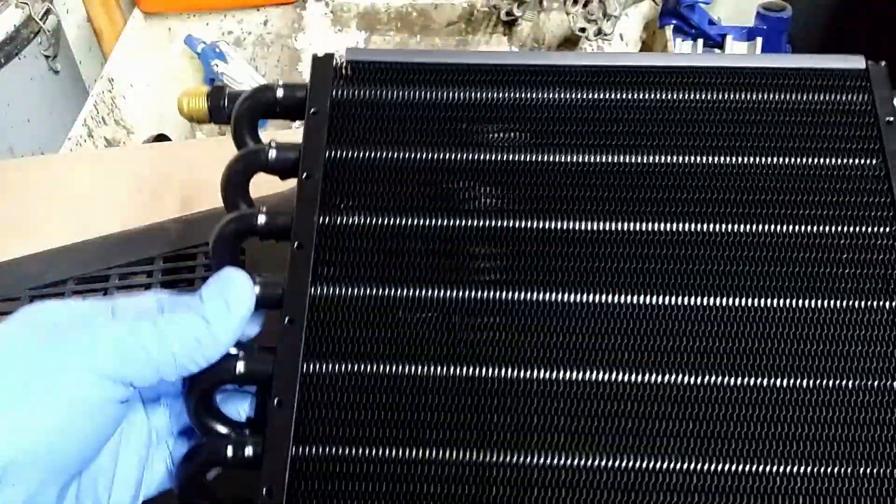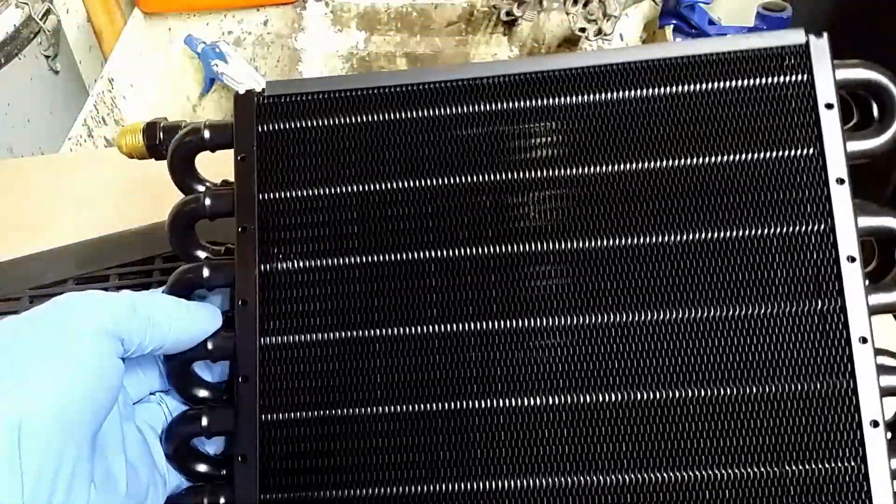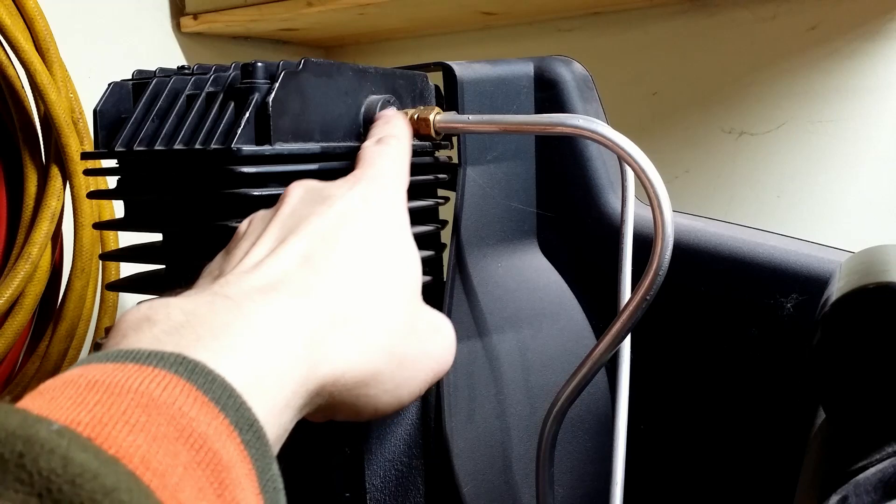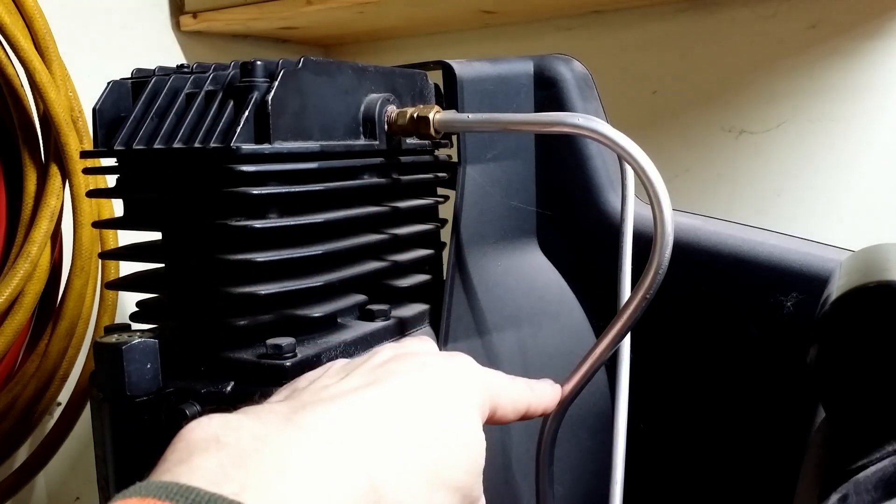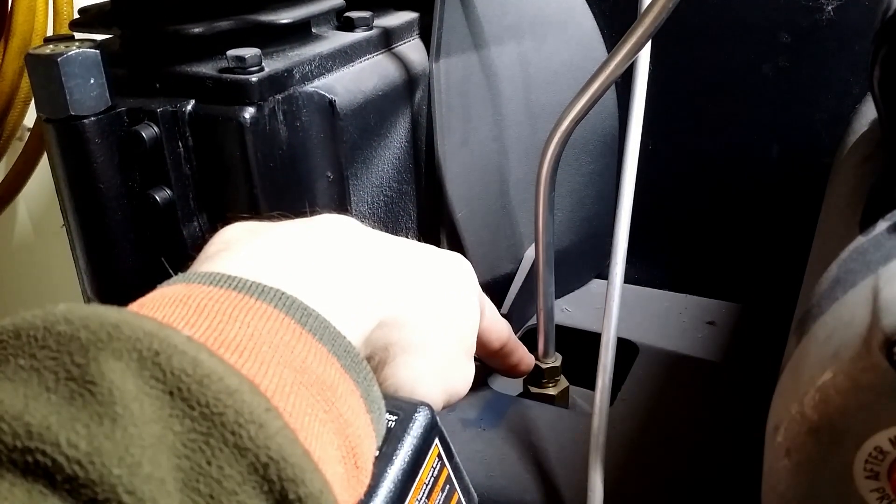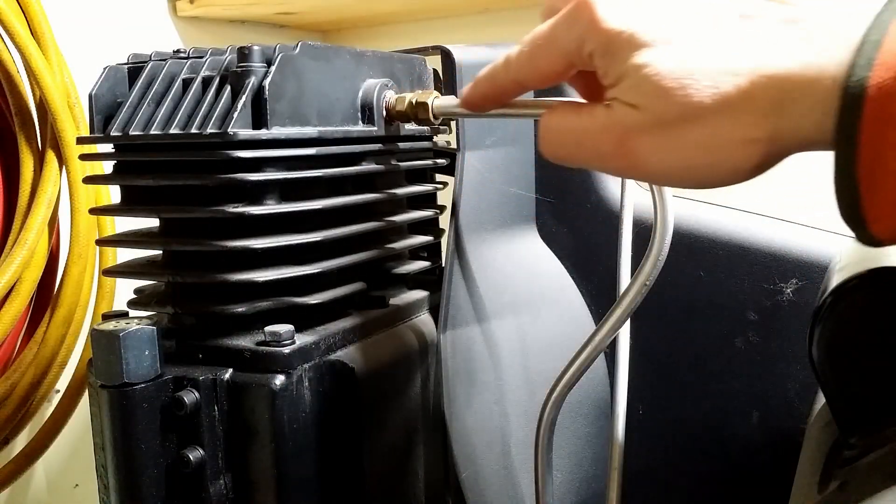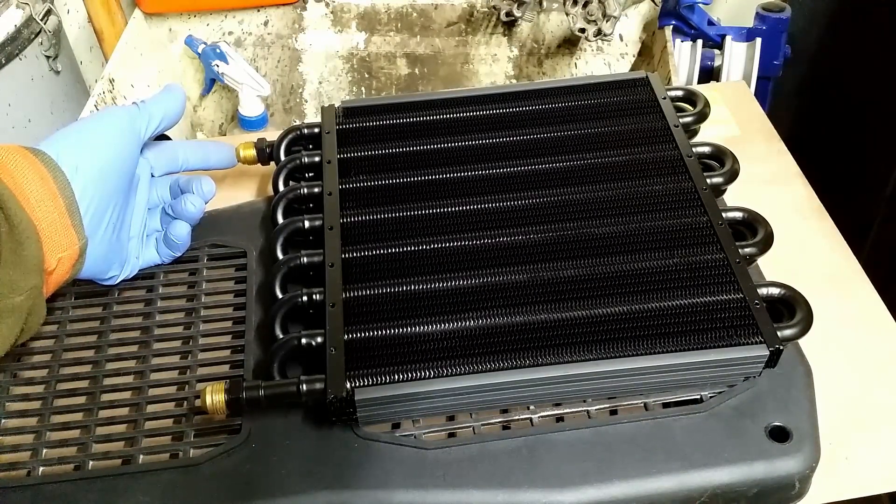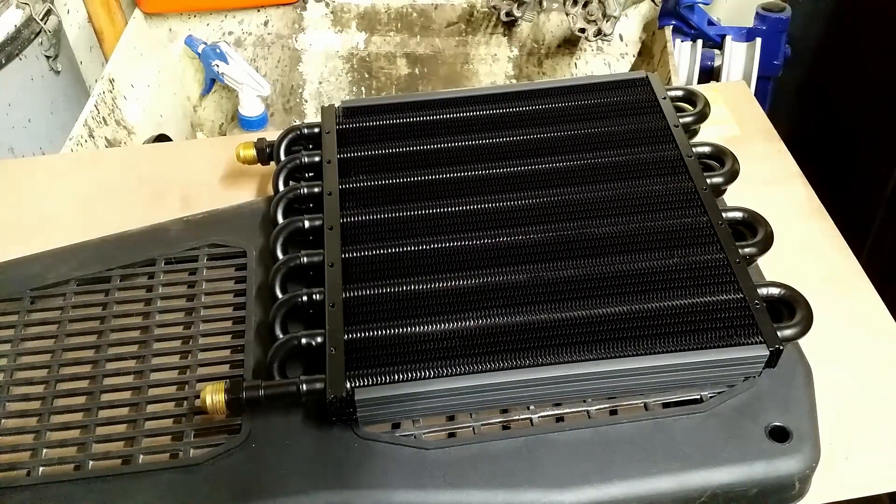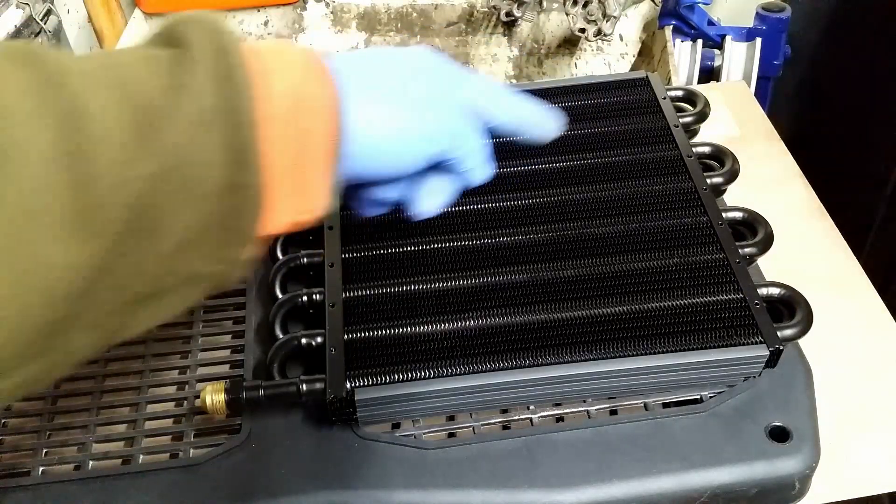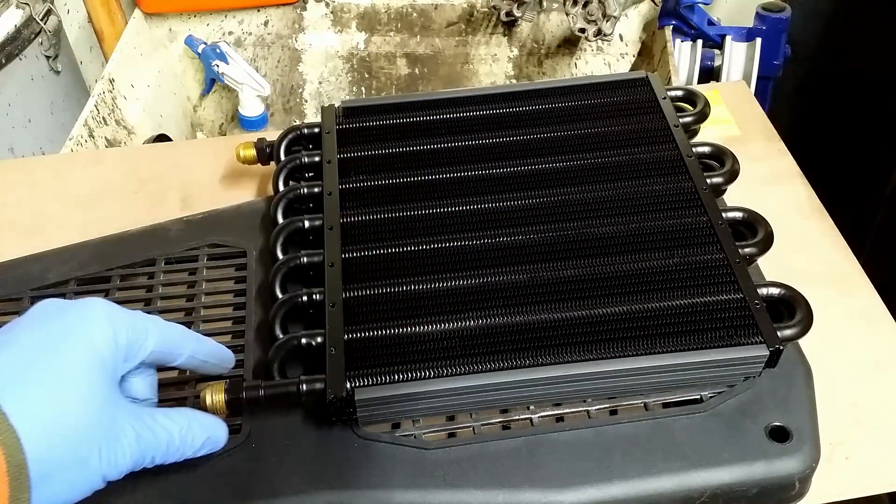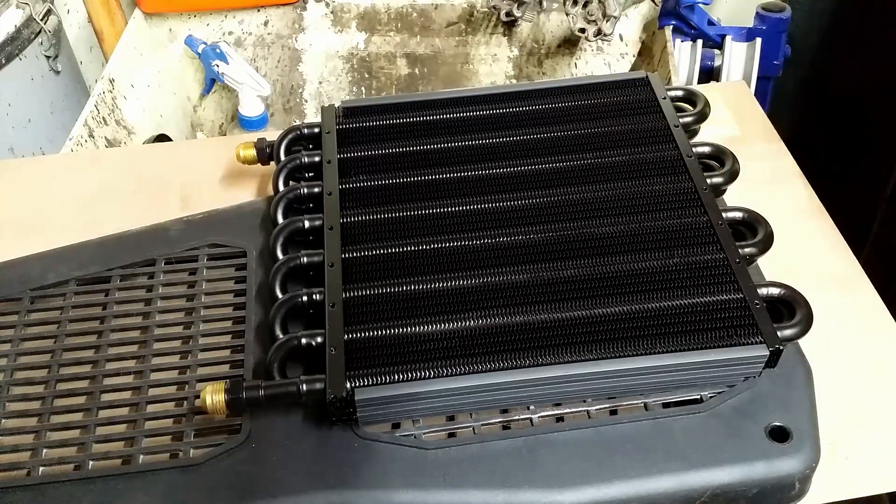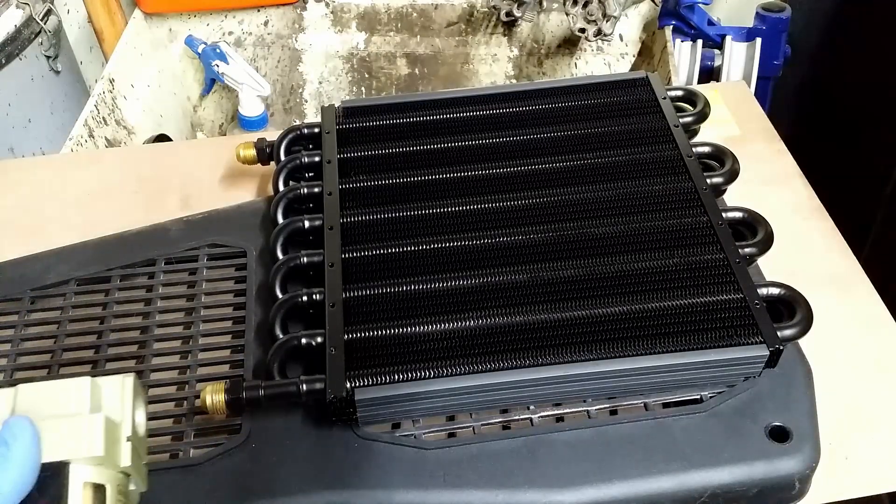As part of this project I will install this cooler to reduce water in the system. In the factory setup the air goes from the compressor straight to the tank. In the new setup the air will go from the compressor to the top port of the cooler. The cooler is rated at 250 PSI working pressure. The air will pass 16 times back and forth. As the air will cool down the moisture inside will go from vapor to liquid and will flow into such a filter.